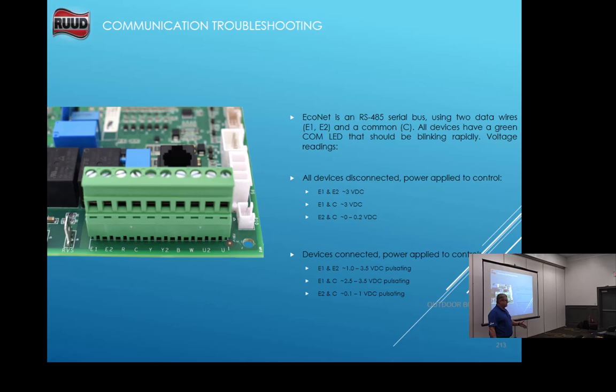If you check these connections, you have to do that. You can't just look at them. You've got to pull them out. If they're in wire nuts, take the wire nut off, bring you a new wire nut, strip the wires back, and redo the connection. Because if you don't, it's going to bite you in the butt.